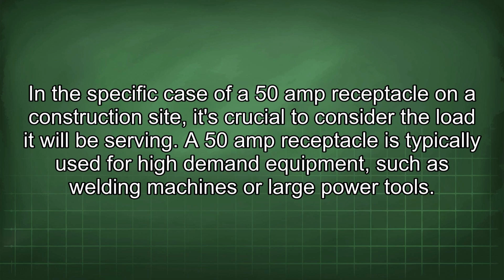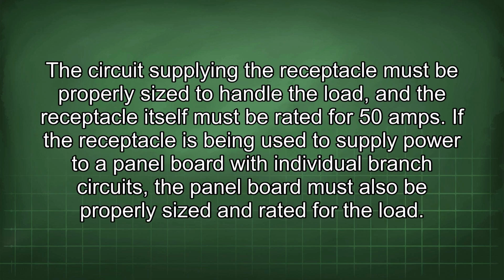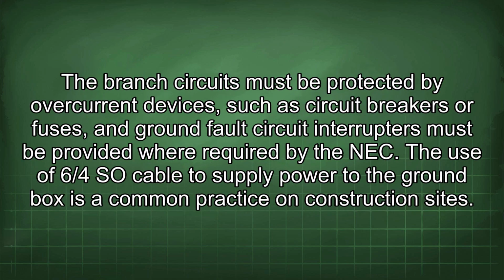electrical shock. In the specific case of a 50-amp receptacle on a construction site, it's crucial to consider the load it will be serving. A 50-amp receptacle is typically used for high-demand equipment, such as welding machines or large power tools. The circuit supplying the receptacle must be properly sized to handle the load, and the receptacle itself must be rated for 50 amps. If the receptacle is being used to supply power to a panel board with individual branch circuits, the panel board must also be properly sized and rated for the load. The branch circuits must be protected by overcurrent devices, such as circuit breakers or fuses, and ground fault circuit interrupters must be provided where required by the NEC.